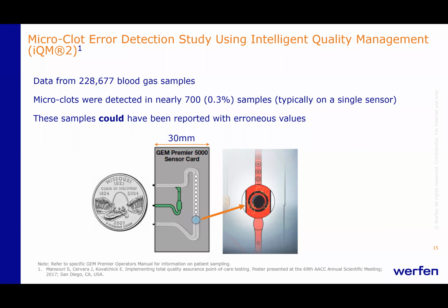So if you think about that, that's 3 samples per 1,000 that, if the microclots hadn't been detected, then erroneous values could have been acted upon for those patients. That doesn't sound like a lot, does it? 3 in 1,000, but if you do 10,000 blood gases a month, 120,000 a year, you can see that number becomes very significant. These samples could have been reported with erroneous values.